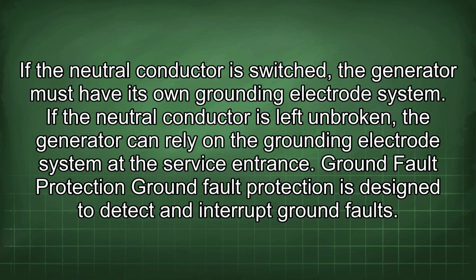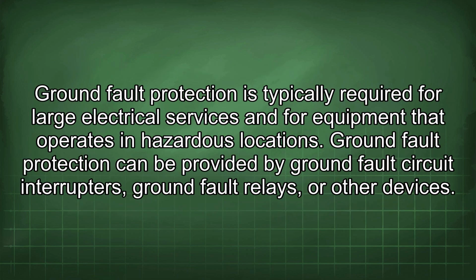If the neutral conductor is left unbroken, the generator can rely on the grounding electrode system at the service entrance. Ground fault protection. Ground fault protection is designed to detect and interrupt ground faults. Ground fault protection is typically required for large electrical services and for equipment that operates in hazardous locations. Ground fault protection can be provided by ground fault circuit interrupters, ground fault relays, or other devices.